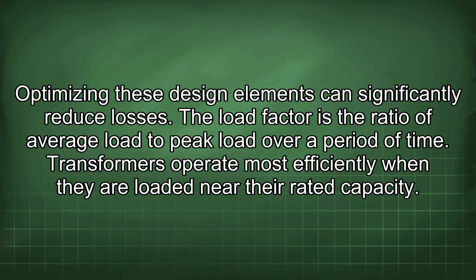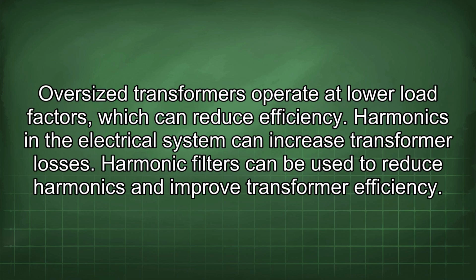Transformers operate most efficiently when they are loaded near their rated capacity. Oversized transformers operate at low load factors, which can reduce efficiency. Harmonics in the electrical system can increase transformer losses. Harmonic filters can be used to reduce harmonics and improve transformer efficiency.